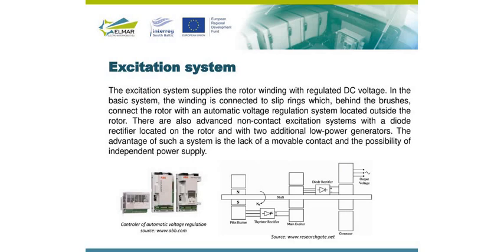And the important element of the synchronous generator is the excitation system. The excitation system supplies the rotor winding with regulated DC voltage. In a basic system, the winding is connected to the slip ring, which through the brushes connects the rotor with an automatic voltage regulator system located outside the rotor. There are also advanced non-contact excitation systems with a diode rectifier located on the rotor. We can see this in the figure below. Some power electronic elements are located on the rotor also. And we also have a pilot exciter connected with the main exciter by a thyristor rectifier. So this is a solution for a brushless excitation system.